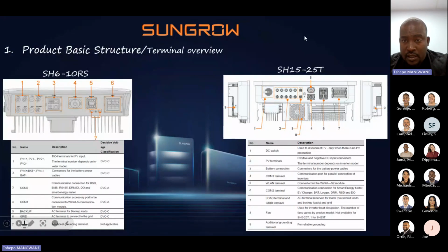Good. Coming to the 15 and 25. Let me do this. 15 and 25, they're all the same as well. It comes with 3 MPPTs. Not to forget to mention, this is a three phase inverter, so you don't need to bother about phase balancing and stuff. Obviously, you can't exceed the maximum capacity of each and every phase. So if it's a 15 kilowatt, you can only do 5 kilowatt per phase. Okay, you cannot put 6 or 7 per phase.